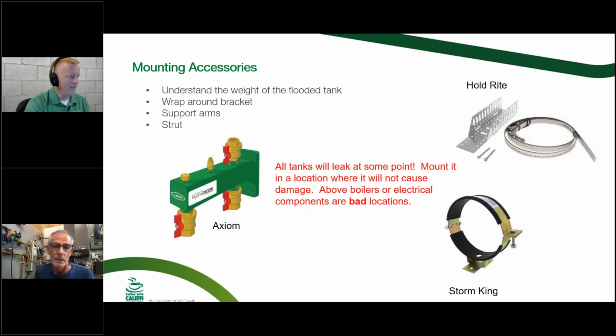But more than anything, make sure that you're supporting the tank. That's code in just about everywhere. You need to make sure it's supported. You don't want to hang it off of a 1/2-inch copper line. If the diaphragm were to rupture for whatever reason, you need to make sure that you can support that weight of the water. So yeah, obviously you've got some brackets here. Anybody could have a favorite, but as long as you're supporting it, I think you're in good shape.